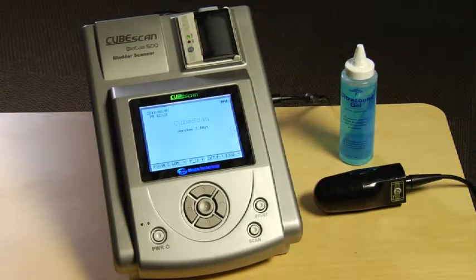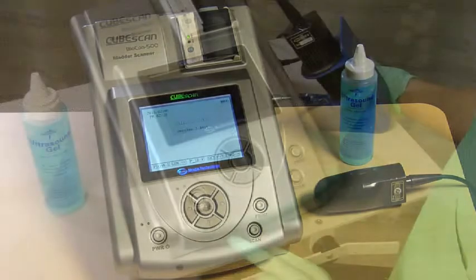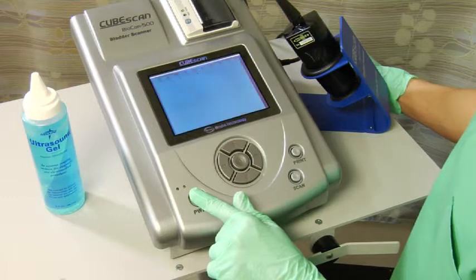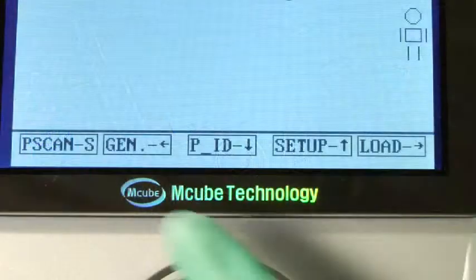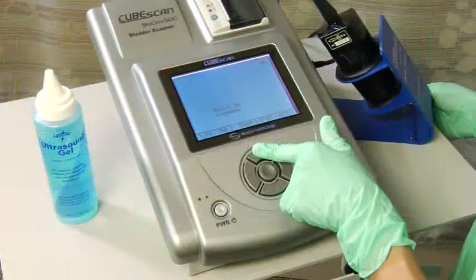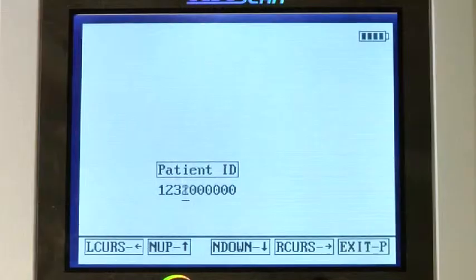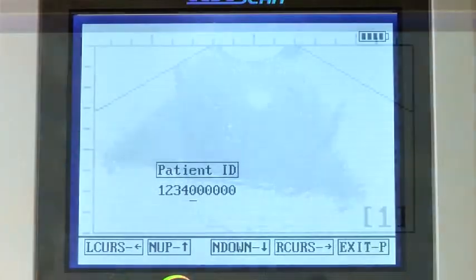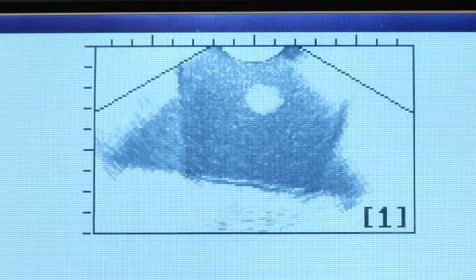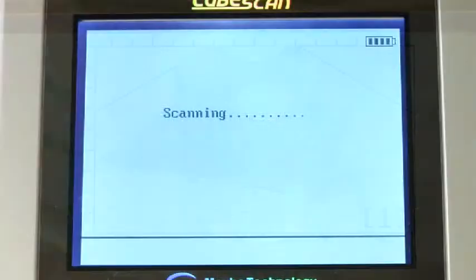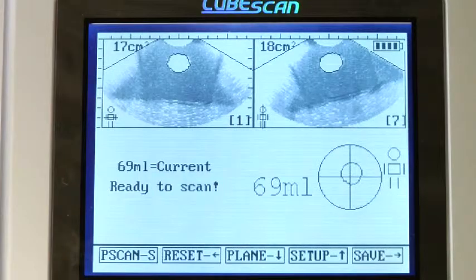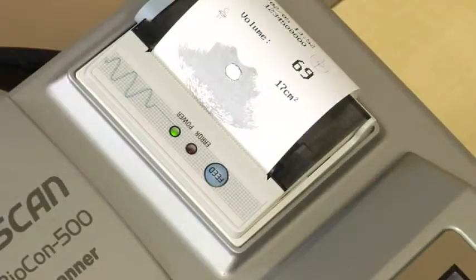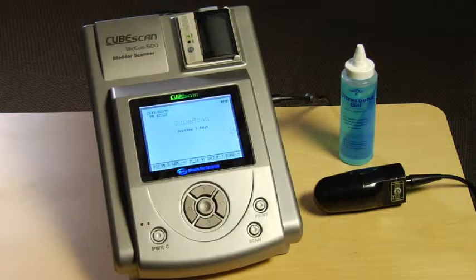The Biocon 500 is very easy to use and requires 6 simple steps. 1. Push and hold the power button until the screen lights up. 2. Select the gender. 3. Input the patient identification number if your facility chooses to do so. 4. Use the pre-scan function to locate the bladder. 5. Scan the bladder. And 6. Record or print the results. The whole process takes just a few minutes. Let's take a closer look at how it works.